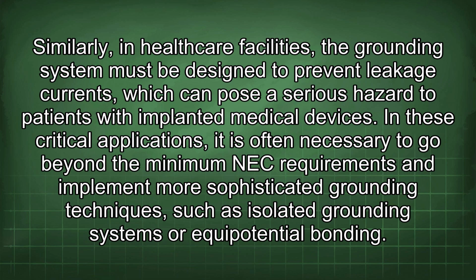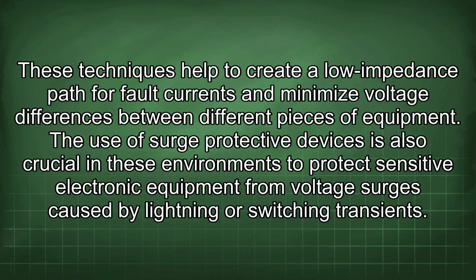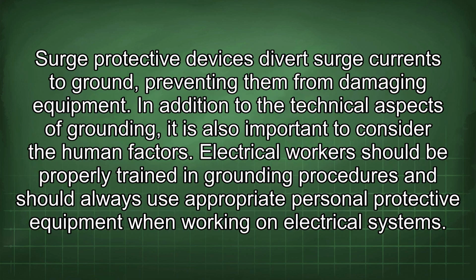In these critical applications, it is often necessary to go beyond the minimum NEC requirements and implement more sophisticated grounding techniques such as isolated grounding systems or equipotential bonding. These techniques help to create a low impedance path for fault currents and minimize voltage differences between different pieces of equipment. The use of surge protective devices is also crucial in these environments to protect sensitive electronic equipment from voltage surges caused by lightning or switching transients. Surge protective devices divert surge currents to ground, preventing them from damaging equipment.